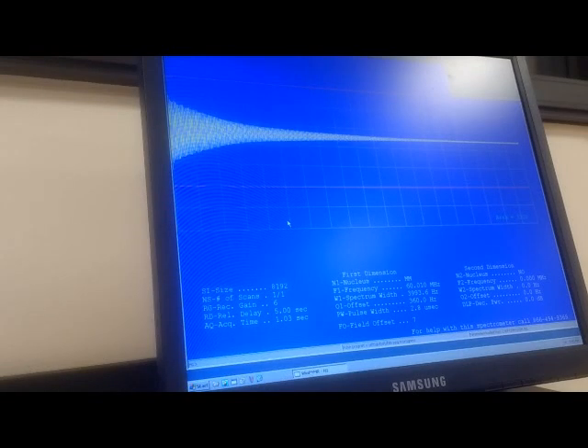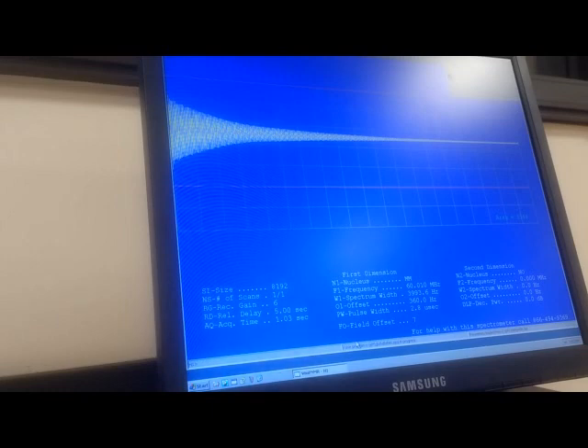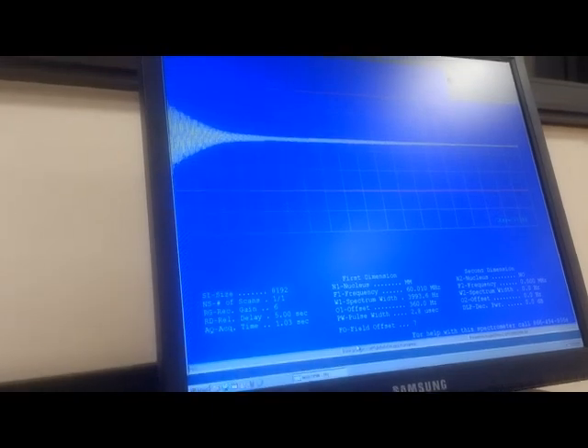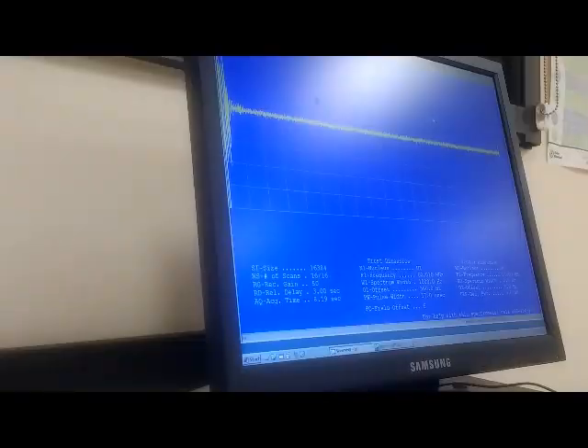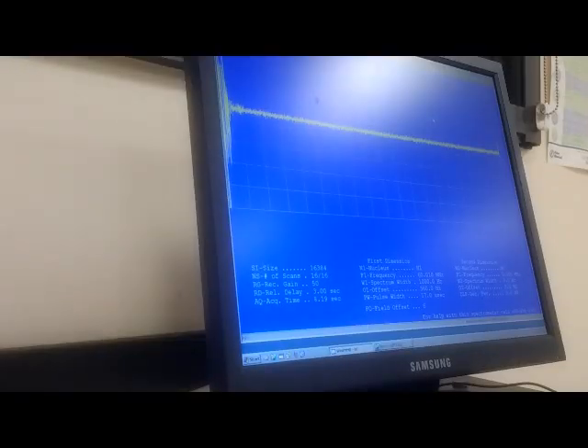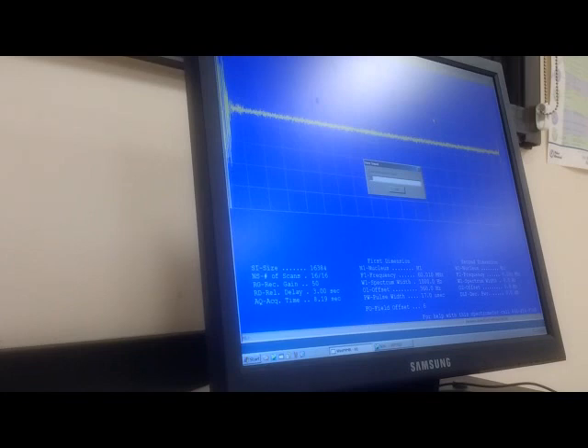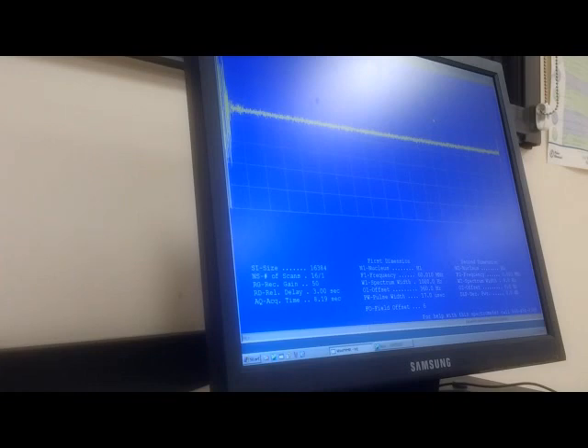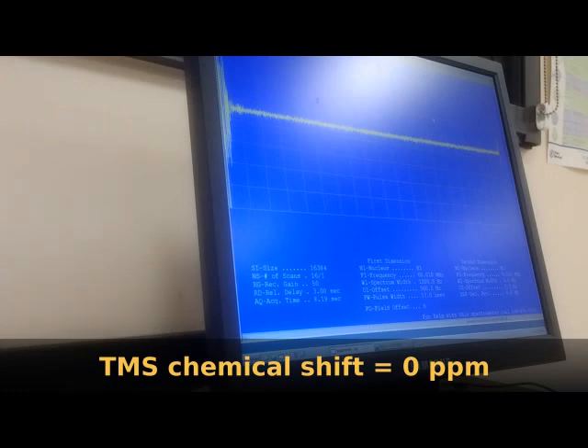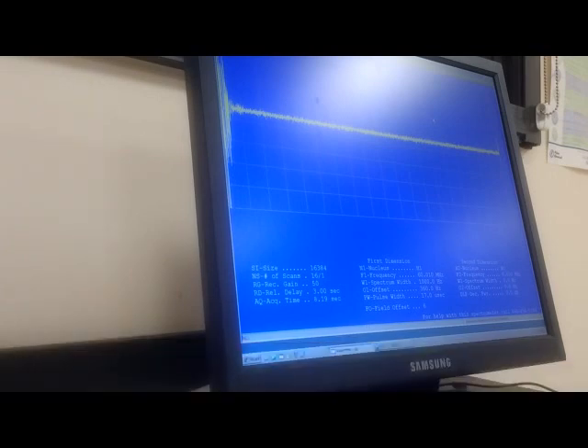While the shimming is in progress, I don't know if you can see, at the bottom of the screen, it'll say pulse program shim is in progress. And it'll take a few minutes to complete. Now that you're done with the shimming process, what you want to do is to type in NS. And that sets the number of scans. We want to just run one scan. And the reason for that is we will want to see whether or not the calibration for the chemical shift is on point or on target, or where it's supposed to be. You should have some TMS or tetramethylsilane standard already dissolved in your deuterated chloroform solvent. And because of that, you should see a TMS peak. And we want that to be exactly at zero ppm. So what we want to do is to go ahead and start the acquisition ZG.